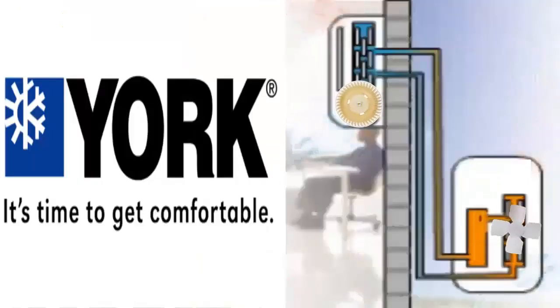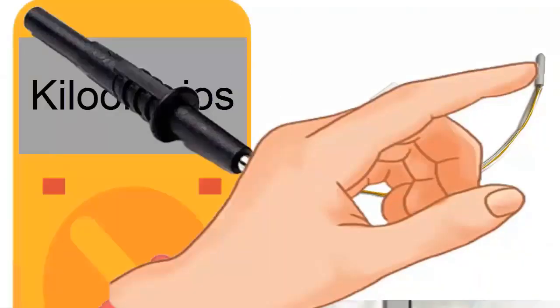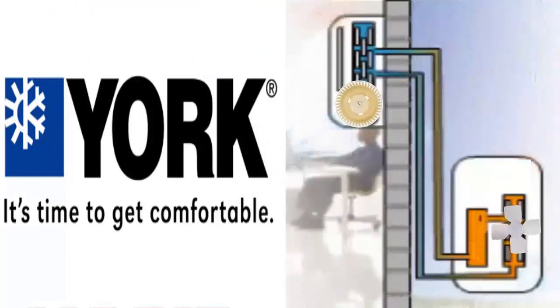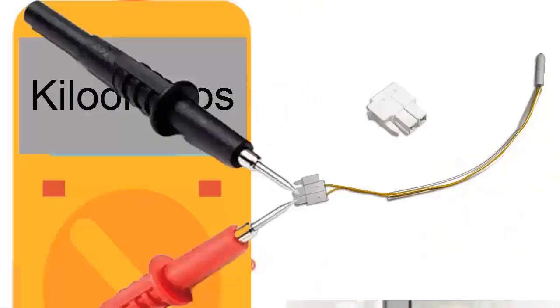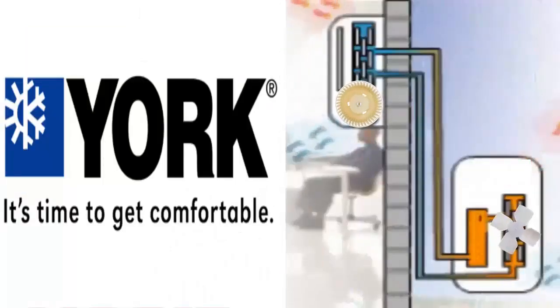Step E: If you have the sensor's resistance and temperature chart, compare the measured value with the chart values. If you don't have the chart, measure the resistance while rubbing the sensor with your hand — the resistance should decrease. Step F: The resistance value should never be zero or infinite. Step G: With the sensor connected and the electronic board powered on, measure the voltage supplied by the board with the multimeter set to the DC voltage scale. This value should be around 2.5 volts.